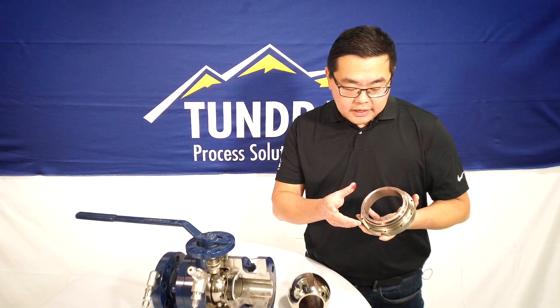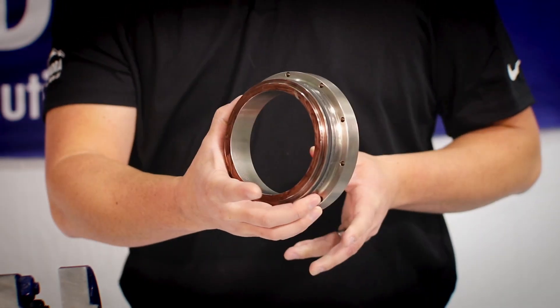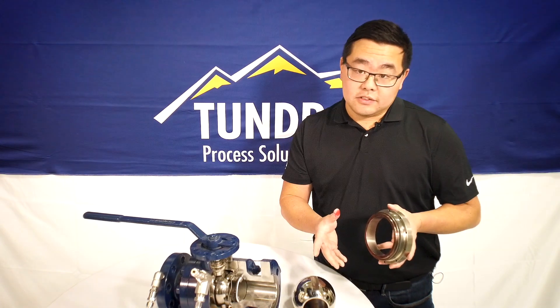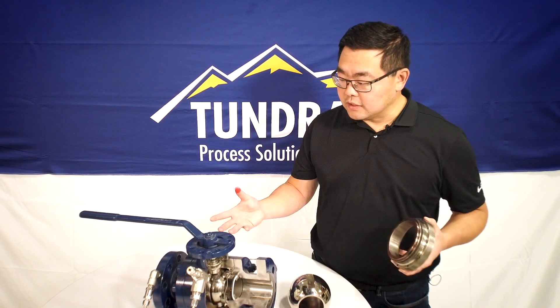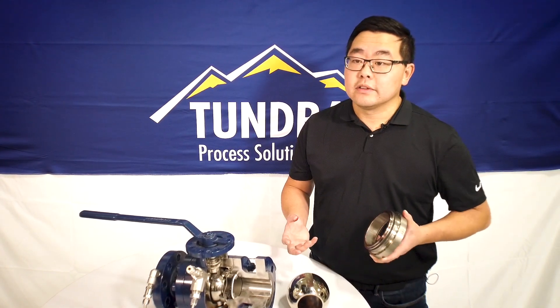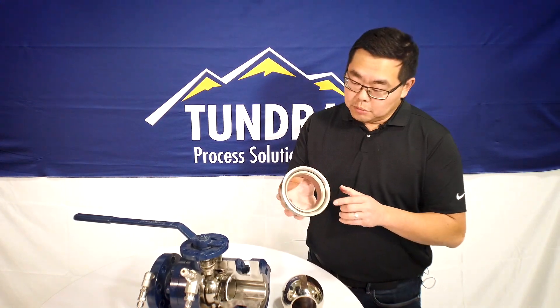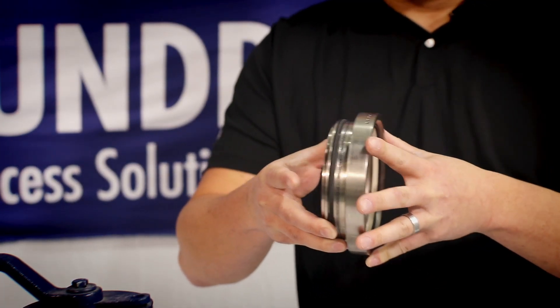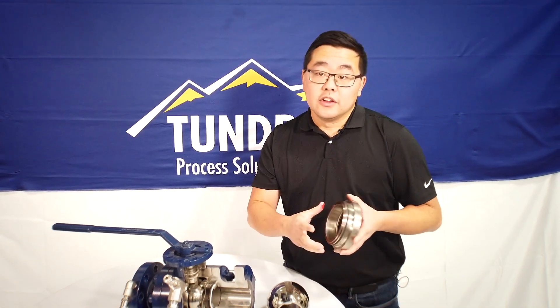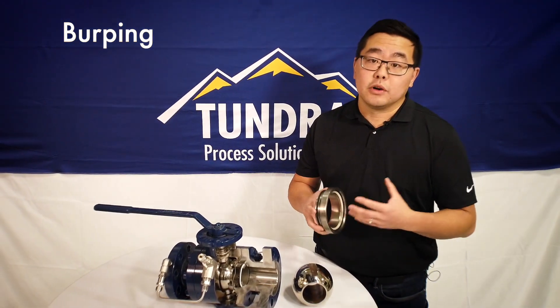The advantage of the single piston effect seat is your process pressure acts on this back face, pushing the seat carrier into the ball. However, one disadvantage is these seat carriers typically burp, due to the fact that they can be overcome by internal cavity pressure. If you close your valve with liquid inside, you can get liquid thermal expansion — say a condensate that wants to turn into a gas. That gaseous process fluid will push on this face of your seat carrier and overcome the process pressure, pushing it back. That's called burping, and it relieves the pressure in the center cavity of the valve, essentially protecting your valve.